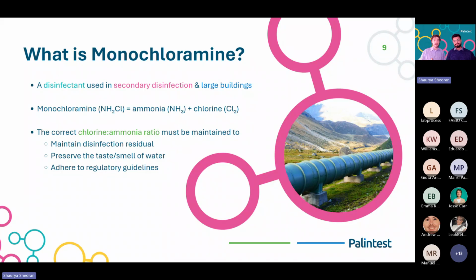If you have too much chlorine in the sample, that can lead to the development of harmful di- and trichloramines, which can affect the taste and smell of the water. And if you have too much ammonia in your mixture, that can lead to nitrification in the pipes and a buildup of biofilm, which can also affect taste and odor and cause safety issues. So the main takeaway is monochloramine is a stable disinfectant used in long pipe networks, and it's better for preserving taste and smell.